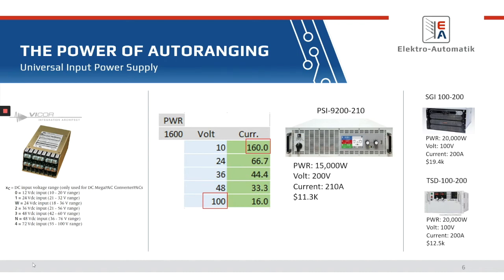You get your 20 kilowatts. And likewise down below. So one of the things you'll notice here, well, probably multiple things, is first, it's a 20 kilowatt versus 15 kilowatts. A lot of times power supplies' cost is $1 per watt. So it's not that auto ranging power supplies are necessarily any less expensive per watt, but you're losing a less powered unit, 15 kilowatts versus 20 kilowatts.